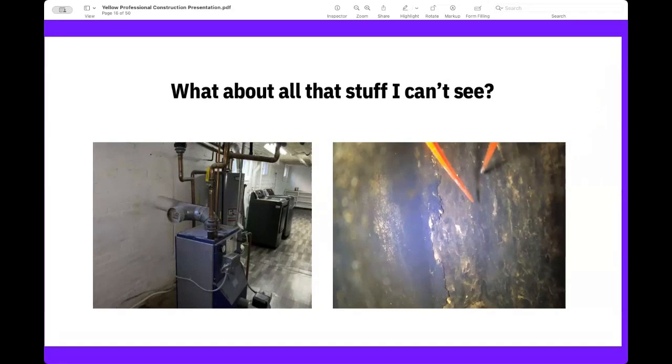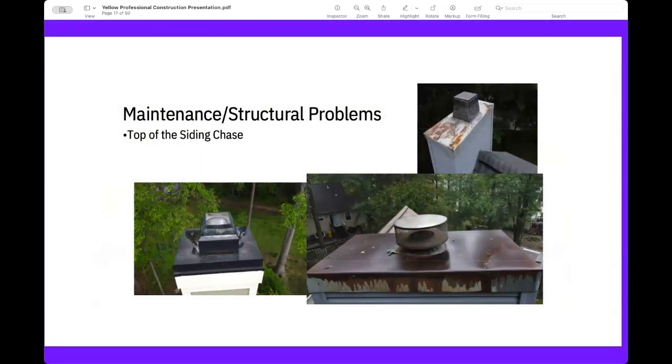Anyway, okay, so this is the inside of that. It's all deteriorated, corroded from the burning of oil. Because they combined the flues, and the chemical composition is not a good combination, and the open chimney at the top getting it wet accelerates the problem.